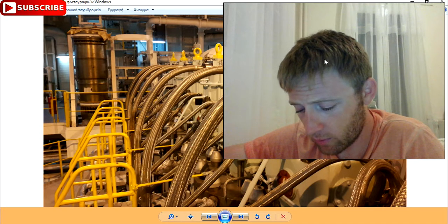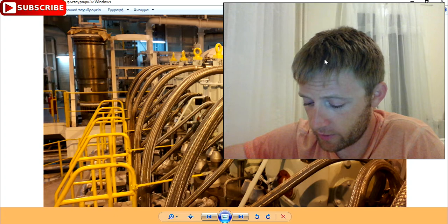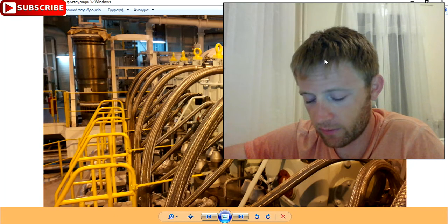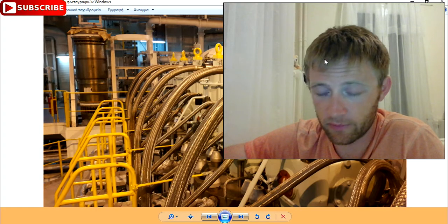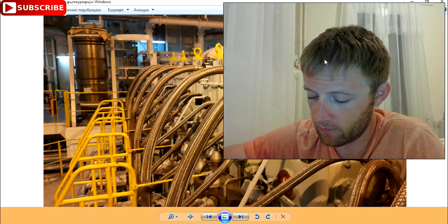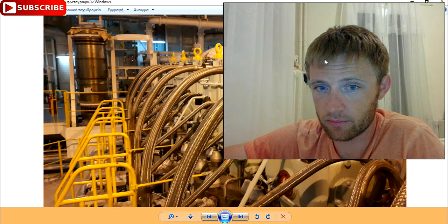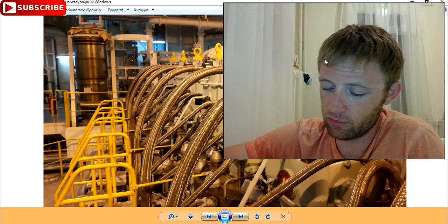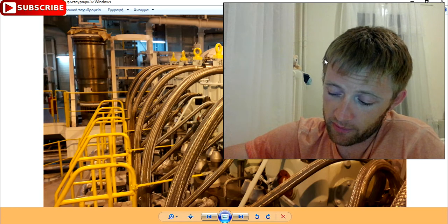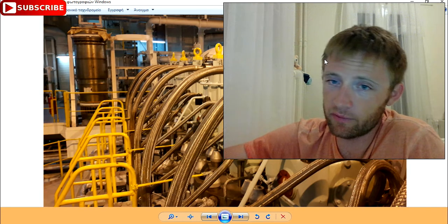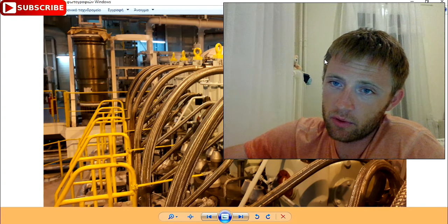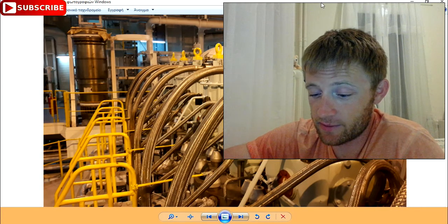Let's go to number four. We never start the pump with a lot of RPM. First, we open the suction. This is correct, because if you have not opened the suction and you have a lot of RPM, you will break the pump, because the torque will be excessive.